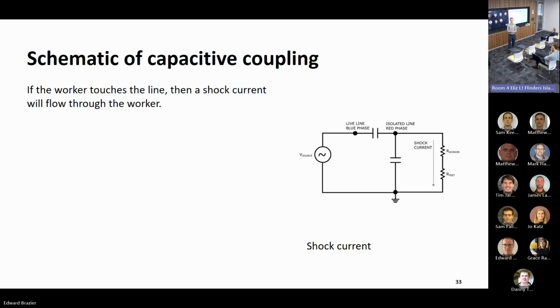So one way of thinking about this is there are maybe two main factors. The open circuit voltage of the isolated conductor is a function not of the length of the line, but of other factors - the operating voltage of the energized line, the distance between the two lines, and some other factors, like Darcy mentioned, the effect of hours.